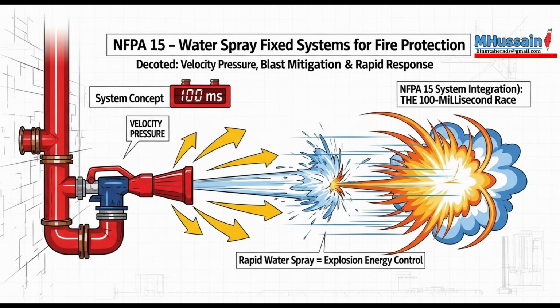And of course, documentation ties it all together. Absolutely. The contractor's material and test certificate is mandatory, 10.1.2. This is the formal document certifying that the installed system complies with the approved plans. It passed the hydrostatic tests, the detection systems operate correctly within their required times, and importantly, it includes the results of that throttling pressure test. It's the official handover confirming the system is ready.